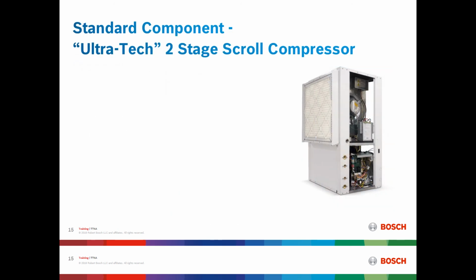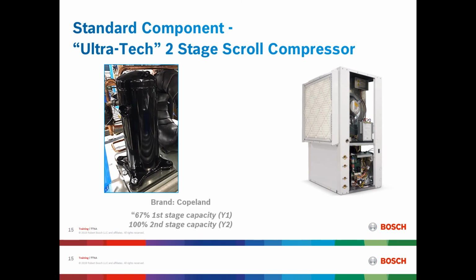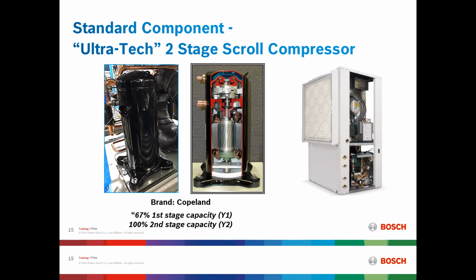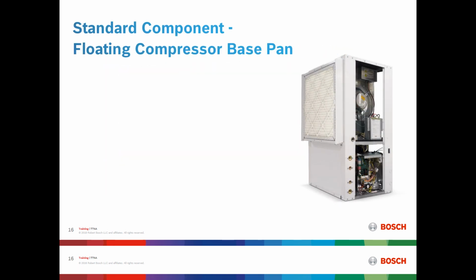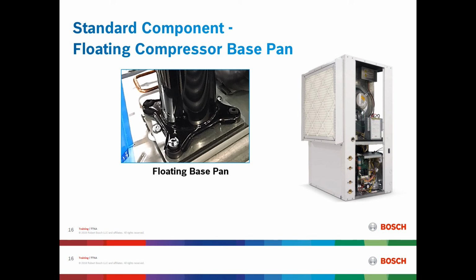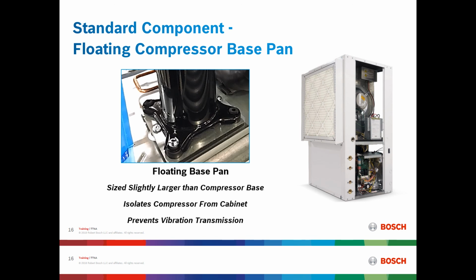Inside the unit, you will have an Ultratech 2-stage scroll compressor. This particular compressor is a brand called Copeland, and it has the ability to run at 67% in first stage, or Y1, in heating or cooling, and at 100% in second stage, or Y2, in heating or cooling. This is a very efficient compressor. Below the compressor will be a floating compressor base pan. This pan is slightly larger than the compressor base and isolates the compressor from the cabinet, therefore preventing vibration transmission.